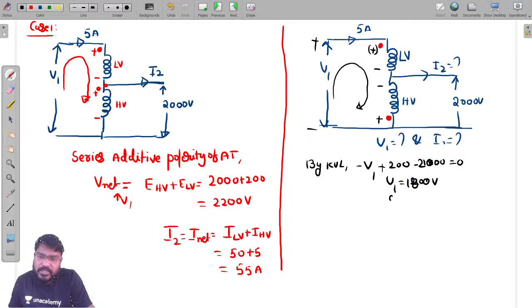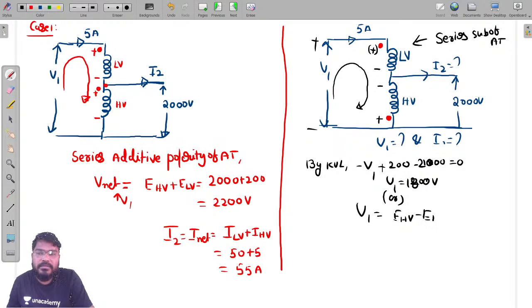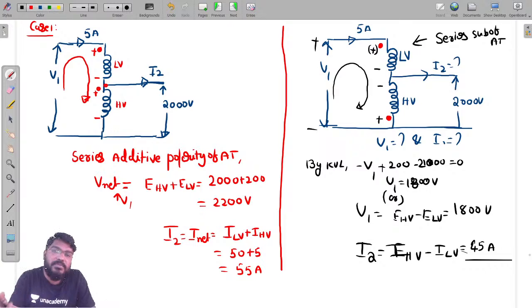Or another way: the net voltage equals the series-subtractive polarity of the auto transformer, that is EHV minus ELV, which equals 1800 volts. Now how is current I2 calculated? It is the difference of these two currents, IHV minus ILV, which equals 45 amps. This is how we calculate it.